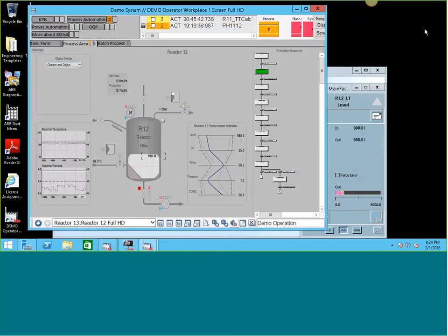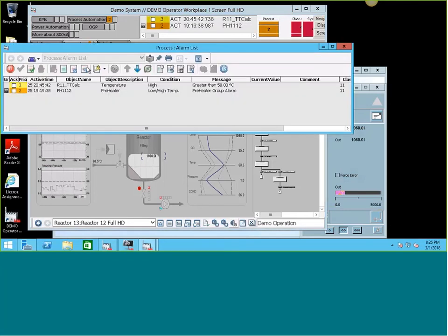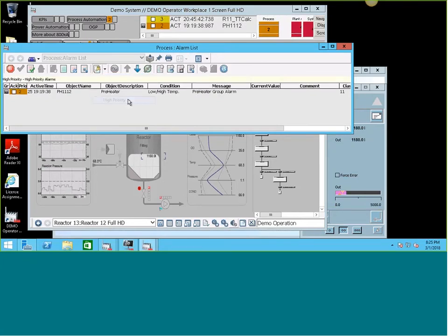And like Roy says, it can also be great for alarm lists, where we can come to an alarm list and set it so for pressure alarms, temperature alarms, or like he said, high priority alarms, where it would only show us priorities over a certain criteria. Like this one's priority 2 and higher. Yes, anything less than 3. Right. That's an example of how we can use these runtime filters to help make our alarm and event lists more user-friendly.